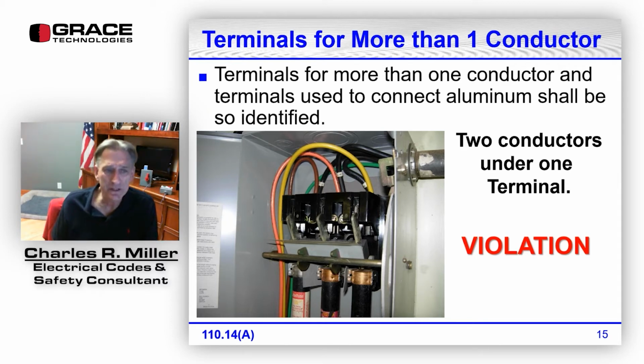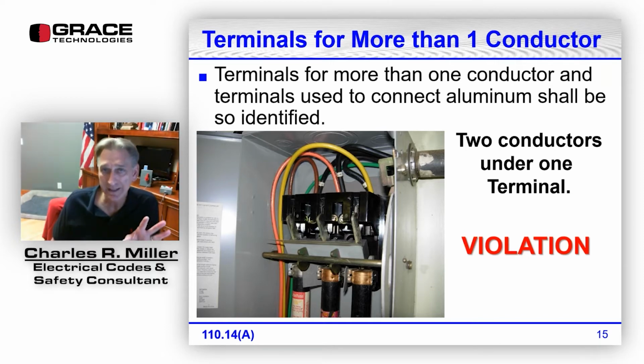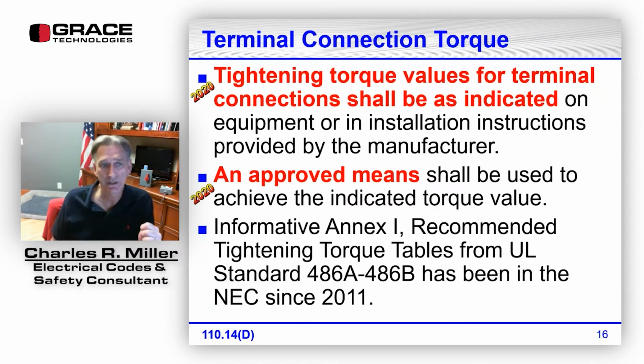Now, if for some reason something needed to be tapped off and there was only one set of lugs there, and it would be permitted to tap off of that, which here there's no way, these are different size conductors, then the lugs would have to be changed out to double barrel lugs or a lug that permits two conductors under one terminal, which you're not going to find. But all right, torque connection.